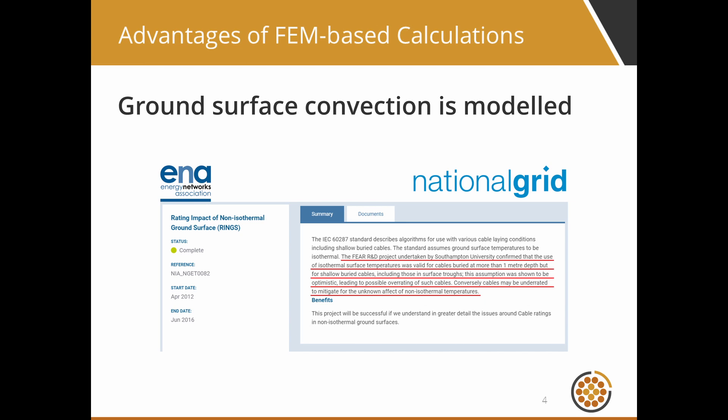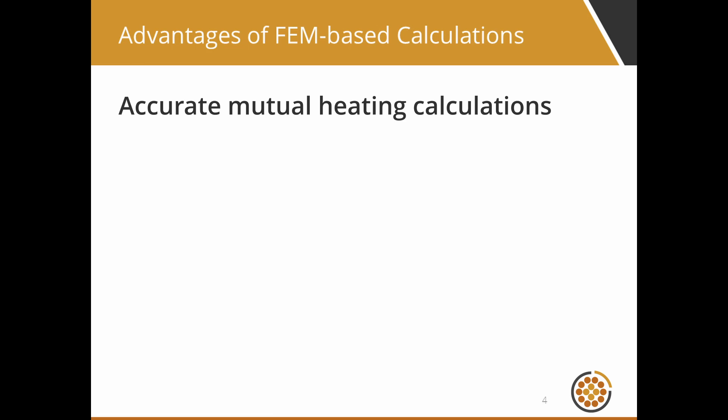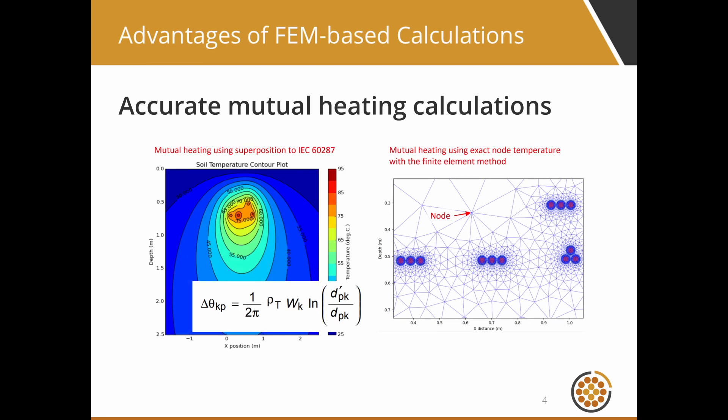A recent study by National Grid using FEM calculations concluded the IEC method overrates cables buried at one metre or less. Thirdly, FEM-based cable rating calculations have accurate ratings for groups of cables. The mutual heating effect for groups of cables is more accurate when using FEM. The IEC standard approach is to calculate the mutual heating for each cable separately and combine heat rise as an algebraic sum using superposition, whereas with FEM the mutual heat flux influence and disturbance are considered simultaneously.